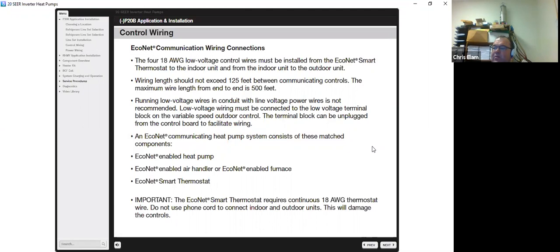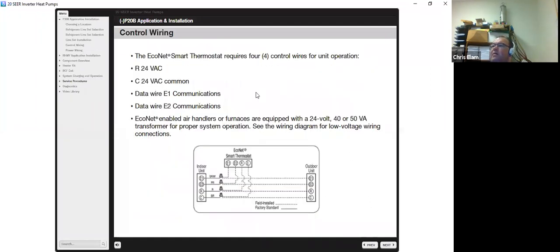When they say continuous 18-gauge wire, they don't want junctions in between point A and B. If you have junctions, it's best to use butt connectors or the butterfly connectors. Standard wire nuts can cause communication errors. So ideally, you want a straight shot from your thermostat to your furnace, from your furnace to your outdoor unit. It only requires 4 wires.